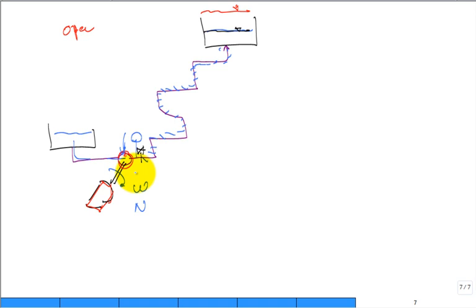Okay? So guess what happened to his pipe? It burst. And where did it burst? Where the pressure was highest, just on the outlet of the pump. Now he has all this fluid that was up there built from yesterday. He has a burst pipe. He just can't close the valve very easily. It's burst. And where does all this water go? And it's a big disaster. So always dump high.